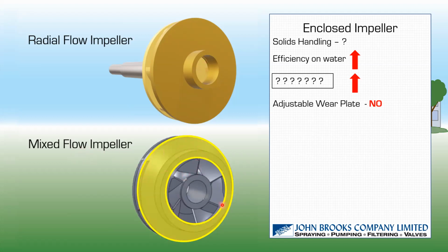So right here is actually a front shroud. So I would say, and do you agree with me, Chris, that this actually could handle solids quite well because you can access the impeller. Yeah, large openings, large suction inlets.